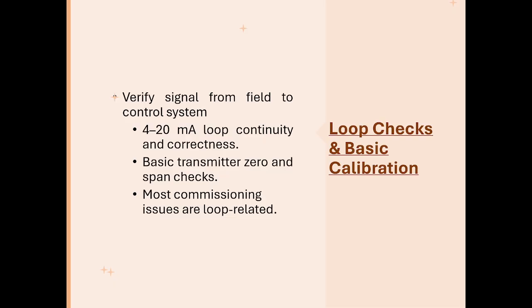So what is a loop check? A loop check is a test that confirms a signal can travel correctly from the field instrument through the wiring into the control system and back out to the final control element. So in simple terms, we are asking: when the instrument changes, does the PLC see it correctly, and does the output respond as expected? Now, basic calibration ensures that instruments report accurate values. Zero and span checks are performed so that what the instrument measures matches reality.